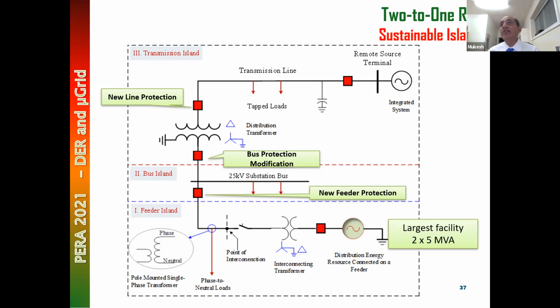Absolutely. The transformer has no problem. You're talking about this distribution transformer, am I right? Yes, sir. So the question is, if I understand, can it work properly in reverse? Absolutely. A transformer has no problem with power flow either way. It's not a generator. A generator cannot work with reverse power flow. If there's a diesel generator, that will explode.